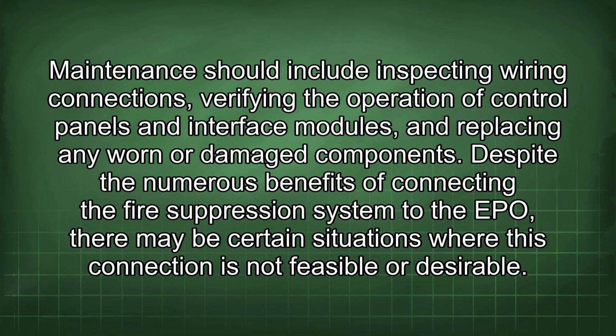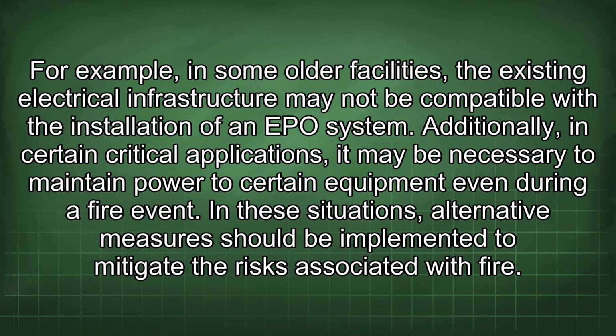Despite the numerous benefits of connecting the fire suppression system to the EPO, there may be certain situations where this connection is not feasible or desirable. For example, in some older facilities, the existing electrical infrastructure may not be compatible with the installation of an EPO system. Additionally, in certain critical applications, it may be necessary to maintain power to certain equipment even during a fire event.